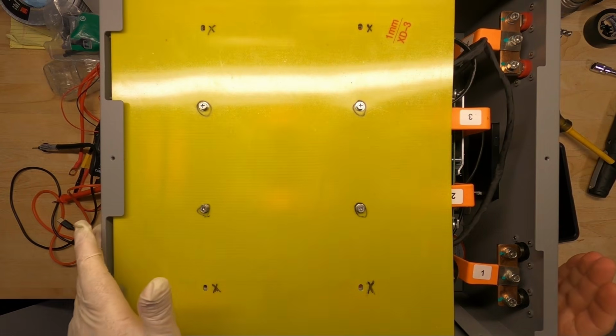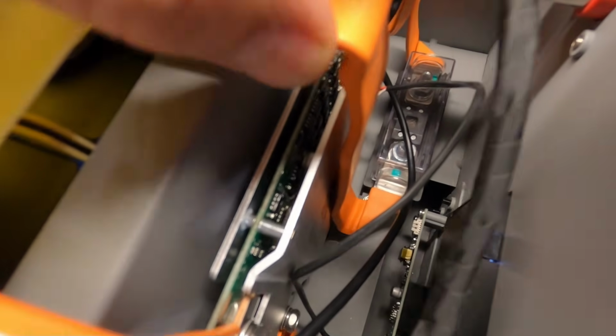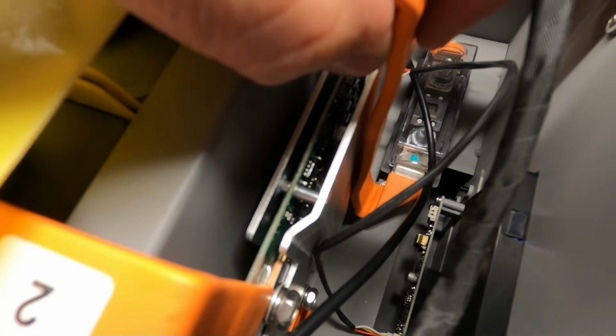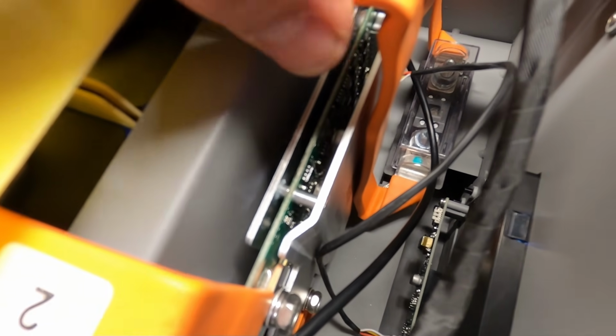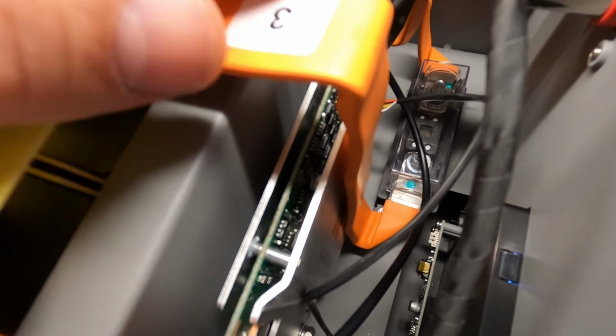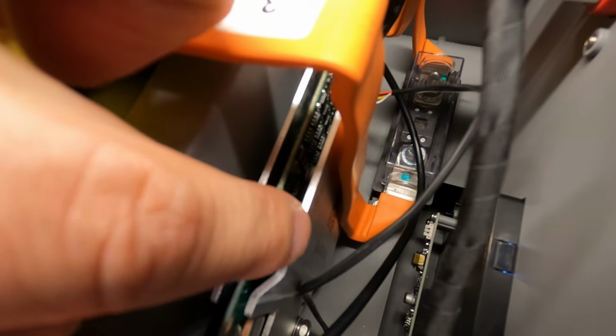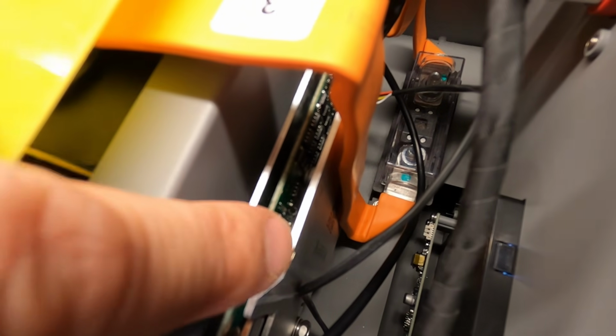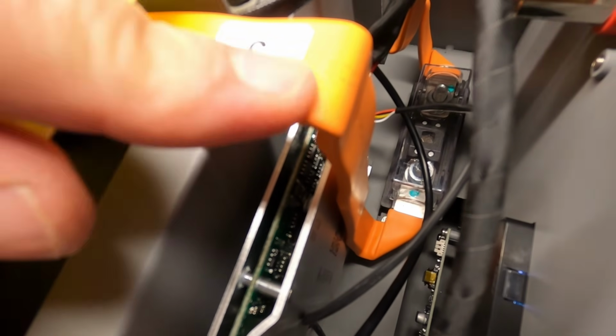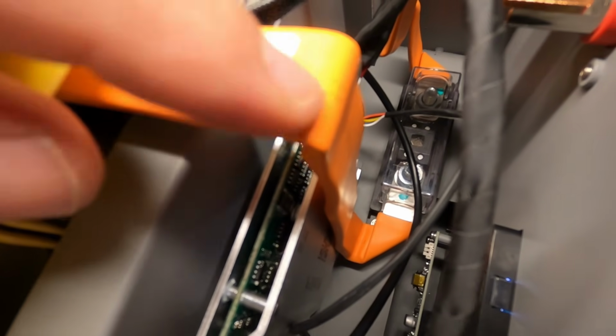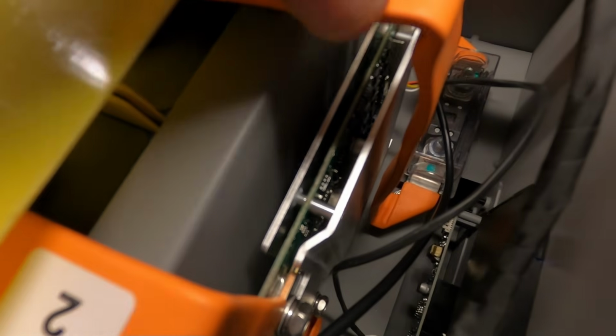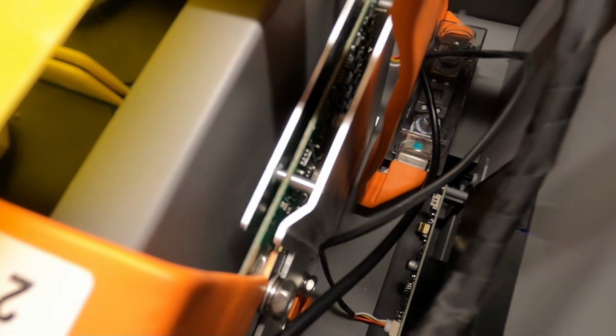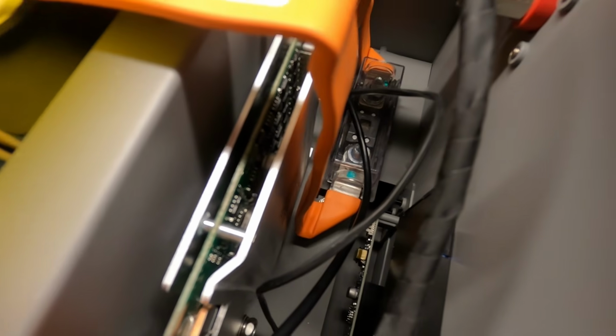Alright, no more sparks. If you notice this bus bar right here, it's practically touching the BMS. Now it is insulated, so it shouldn't be a problem, but these BMS units, if you use them for any length of time at full capacity, can get quite hot. So it's really reliant on the integrity of the insulation to not melt and cause a short. This is something I noticed, so I was able to kick it out a little bit with the screwdriver and got about 1/4 inch of space now. It's a good thing they're flexible.